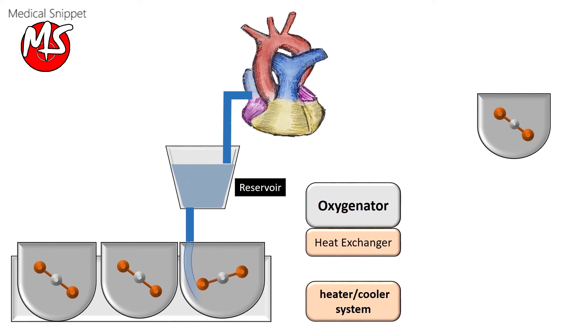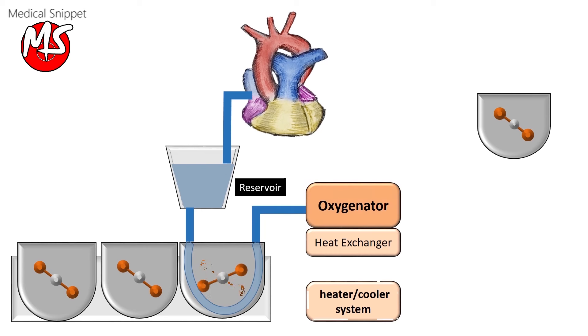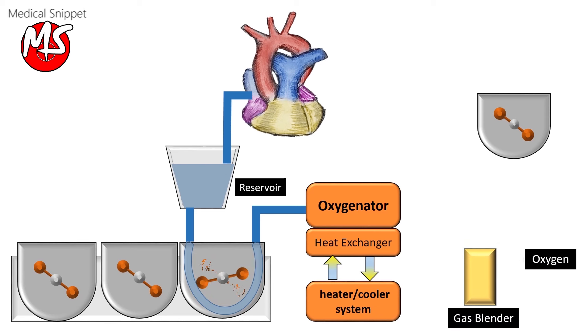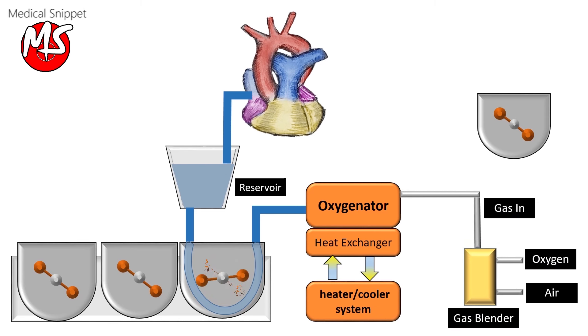From the reservoir, the blood is pumped into the oxygenator by the systemic blood pump. The temperature of the blood can be increased or decreased with the help of a heat exchanger, which is an integral part of the membrane oxygenator. With the help of a gas blender, oxygen and air can be mixed to control the partial pressure of oxygen in the blood. The gas flow, that is the sweep rate, can be adjusted independently to remove carbon dioxide.